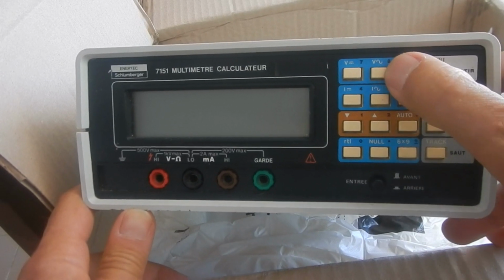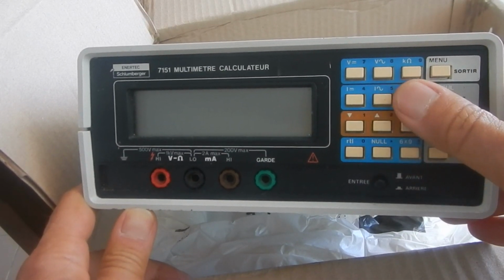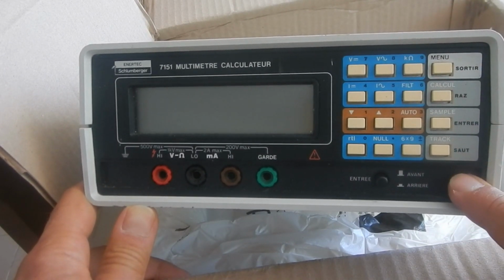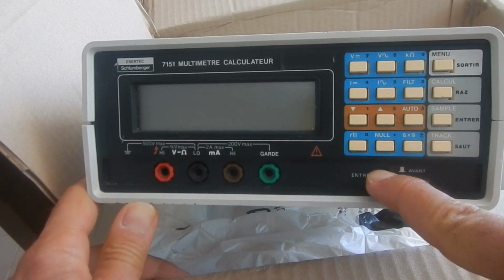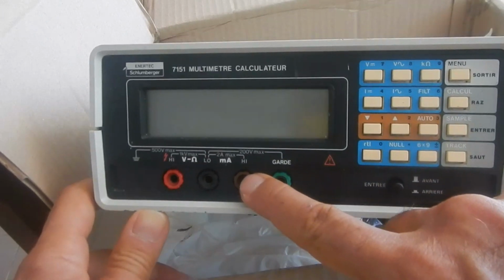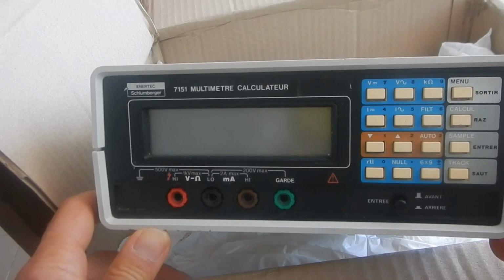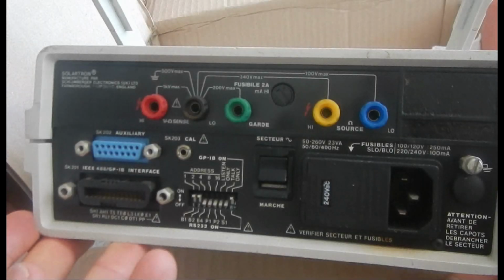All the functions can be selected by this keypad. It has both front or rear inputs, the usual sockets for banana jacks. Let's quickly have a look at the rear panel too. The rear inputs actually are not the same as the front ones. For instance, there is no input for current measurement, but there are the additional inputs to make 4-wire resistance measurements.